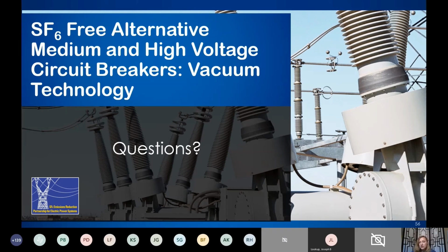So this is Brian Farmer again at PG&E. Yeah, the issue about fill valves has come up. We have not decided to standardize on a specific valve, and part of the reason for that is our SF6 suppliers that we've had throughout the years have different valves on theirs. We don't have a single standard valve for SF6. So what we've allowed is Hitachi to go ahead and use their standard for the vacuum, and what we've done is apply a warning plate adjacent to the valve to indicate that this breaker uses dry air, not SF6. So that's our approach at this point.